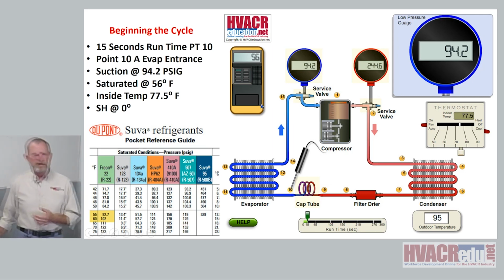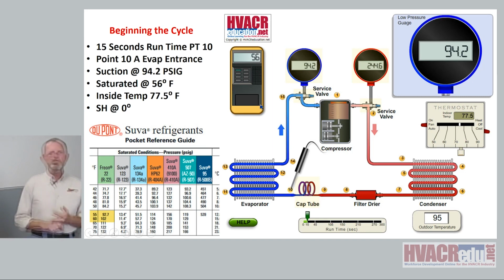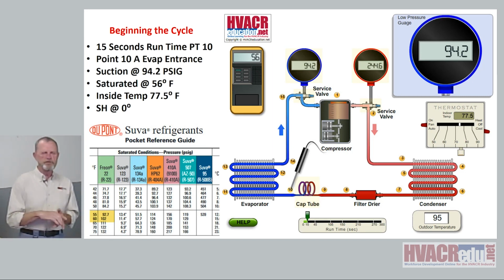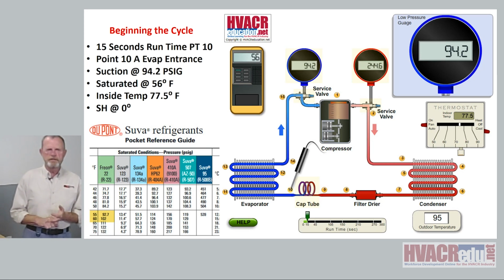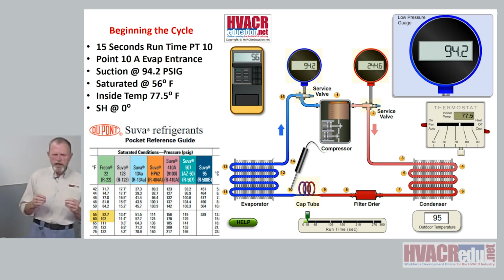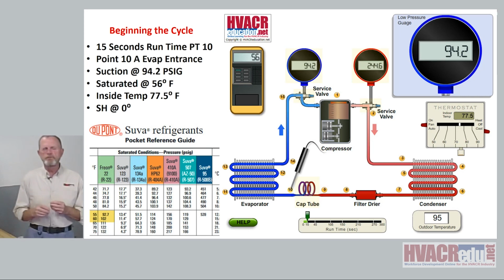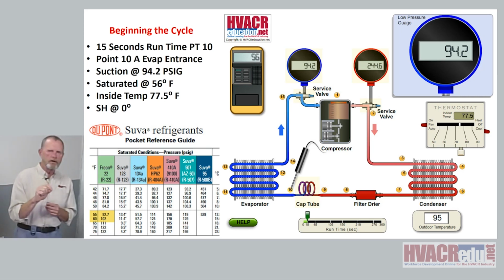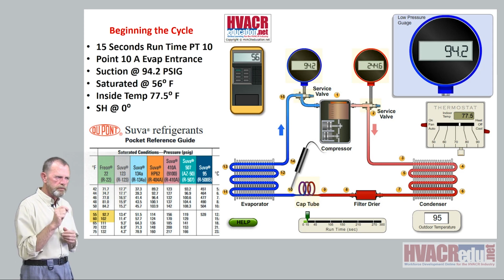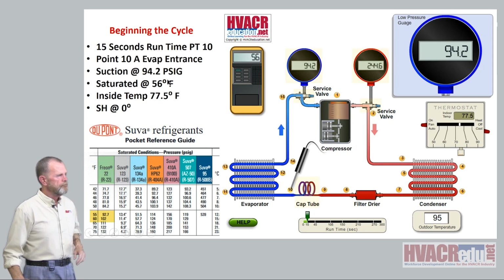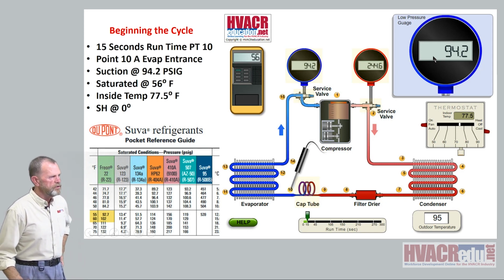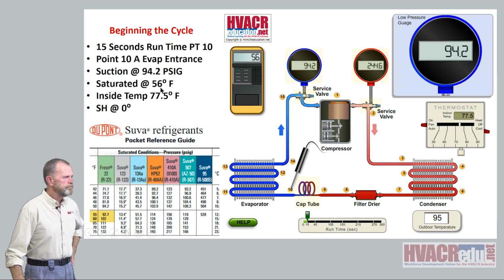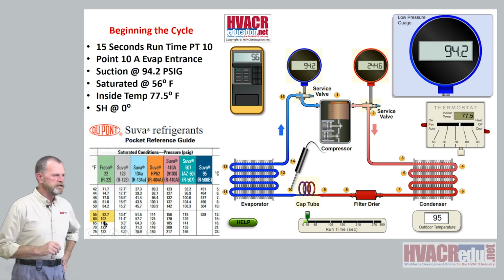How accurate is your electronic thermometer? How often do you check it for calibration? How often do you give it a 32-degree bath to see if it says 32, et cetera, et cetera? Fortunately, by and large, we do not have to be down to the gnat's eyebrows accurate with our measurements. You want to be as accurate as possible, but recognize there's a little bit of twist here. So I'm saying that our suction is 94.2, which I'm reading right off my gauges. That tells me, based on this pressure temperature chart, that I'm at 56 degrees Fahrenheit, saturated condition.